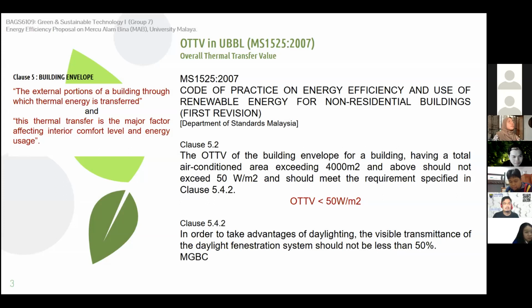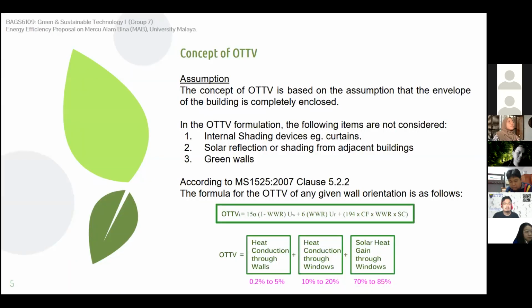The concept of OTTV is calculated with the assumption that the building is completely enclosed, and the following items are not considered: internal shading devices, solar reflections, shading from adjacent buildings, and green walls. The calculation of OTTV is the sum of heat conduction through wall, heat conduction through windows, and solar heat gain through windows.